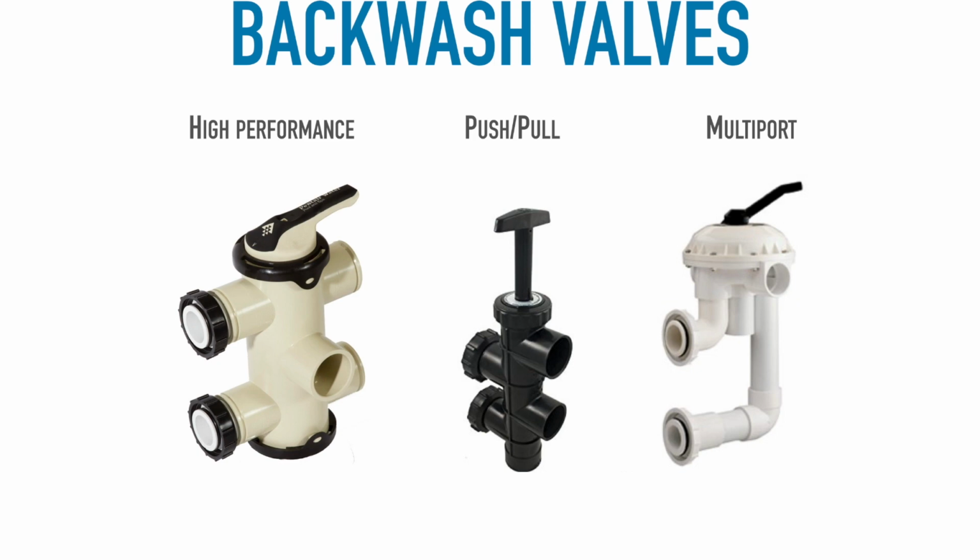Now, they're designed to be able to turn clockwise or counterclockwise, but unfortunately, there's a design flaw in those that if you turn it counterclockwise, you risk ripping up or balling up the spider gasket that's inside of that multi-port, and then you can get water leaking over from one of the other ports into another port. It gets complicated, it gets messy, so this is why we recommend that you just go clockwise.